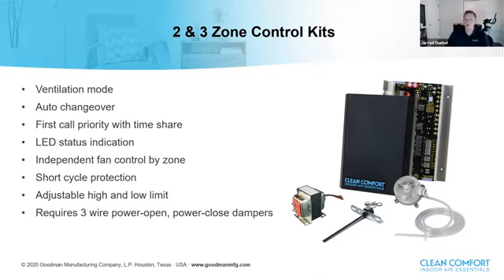So let's say zone 1 is my master bedroom. Zone 2 is a spare bedroom, and then zone 3 is my living area. Well, I spend most of my time in the living area, so I want to ventilate in my living area. So whenever all zones are satisfied, I want to prioritize my ventilation towards that area. Very simply, I would set the zone thermostat in my living area to the fan mode to on or continuous, and then I go to the bedrooms, I would set the fan mode to auto. So what that tells the zone control system or our zone panel is when all zones are satisfied, we're going to go ahead and open the damper to the zone that we've set the fan mode to on or continuous, and then we're going to close the dampers in the zones that we've set the fan mode to auto. So you can get really creative with that feature, and I've talked to a lot of contractors that have done so, especially when you start adding in ventilation systems, UV lights, electronic air cleaners, things of that nature.